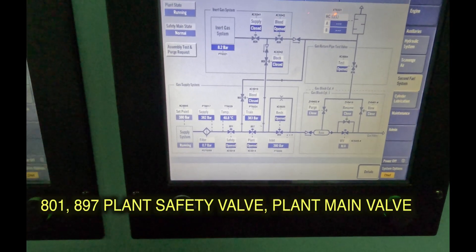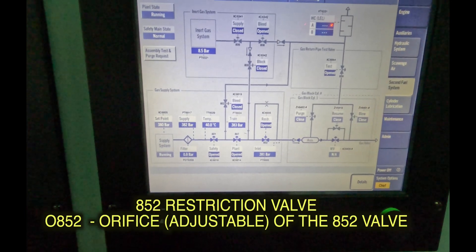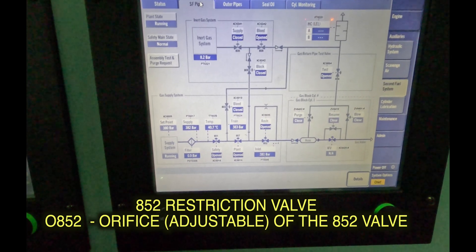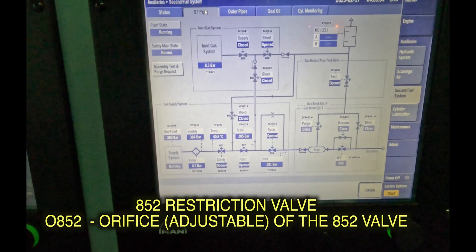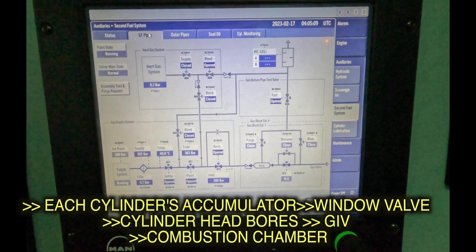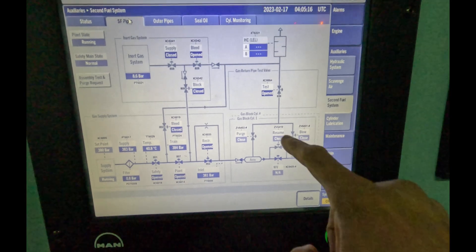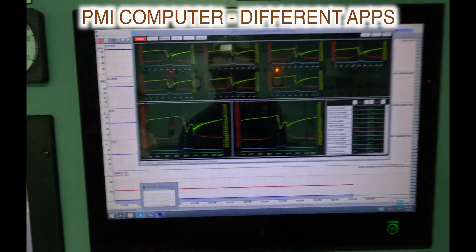801 and 897 are the plant safety valves and the plant main valves. 852 is called your restriction valve — it has a small orifice alongside that is adjustable depending on a few other parameters. That one is called 0852 and the main one is 852. Then it comes into the common manifold, goes into each and every unit, into the accumulators, then the window valves, and then into the cylinder itself via the gas injection valve. This is the venting and purging line — the purging system from the IG.